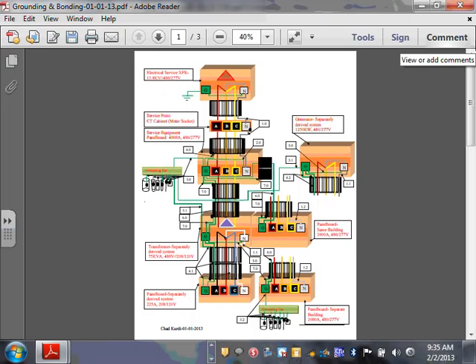But really, the bonding and grounding, other than there's no neutral in a delta, that's it. Ungrounded system, there is no neutral. Everything in bonding and grounding will not change if it was a delta or a delta Y. The only thing that will change is there's no neutral, so you are not going to bond something that does not exist. So there's no bonding to the neutral, right? If you have no neutral, there is no bonding to the neutral. And that will eliminate two things: the main system bonding jumper and the main bonding jumper. These will be eliminated if it was a delta transformer. Any one of them, the top or the bottom.